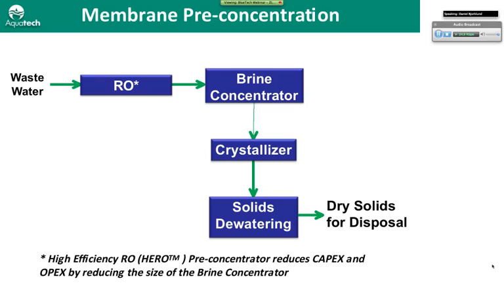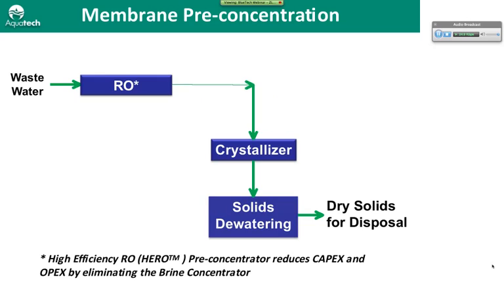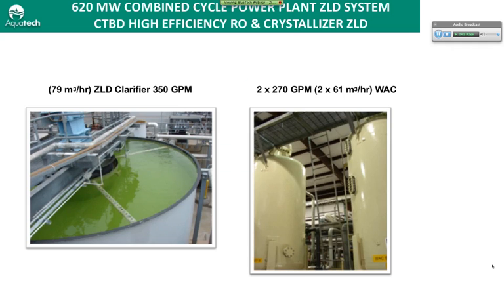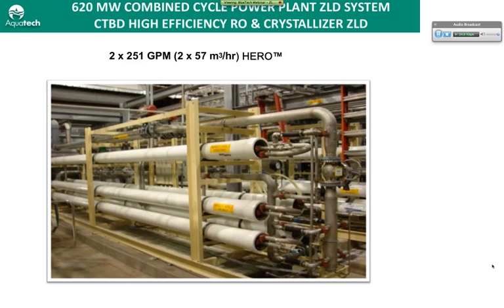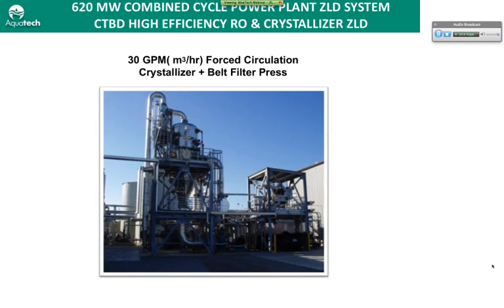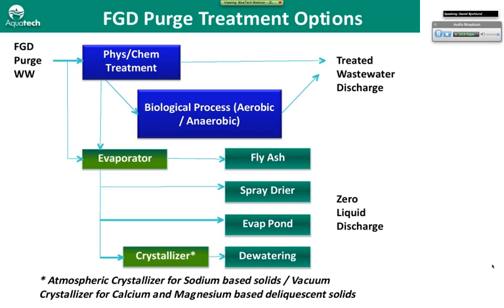As another option, you can reduce the size of the thermal equipment by installing some sort of an RO process. We've got a number of years of experience with the technology with a high efficiency RO process where we get high recovery out of the RO. We reduce the size of the brine concentrator and crystallizer to help optimize the system. And in a lot of instances, we can eliminate the brine concentrator altogether and go directly to the crystallizer from the RO process. That process includes more traditional water treatment equipment: clarifiers, ion exchange, the RO systems, and then finally a crystallizer.